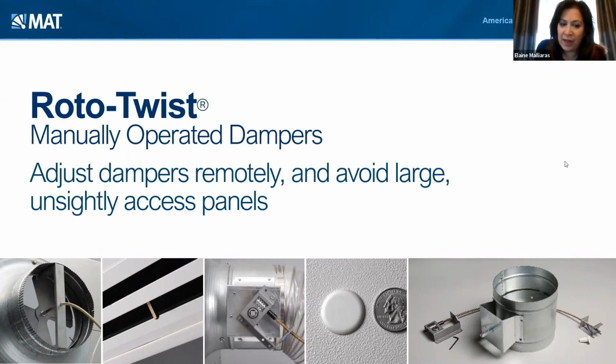Another feature that I like to talk about while we're on this manual damper is that a lot of times contractors will ask if we can lengthen or shorten the cable in the field. And the answer is yes. It's very simple. If you get your dampers out in the field and you discover that it's 2 feet too short or 3 feet too short, we simply send you an extension cable along with a coupling, and you connect the cable in the field and you've lengthened your cable.